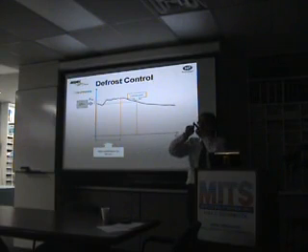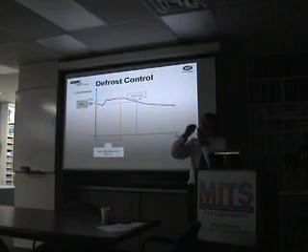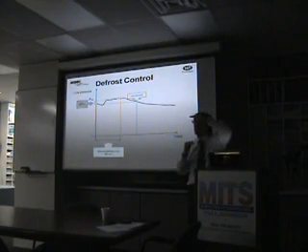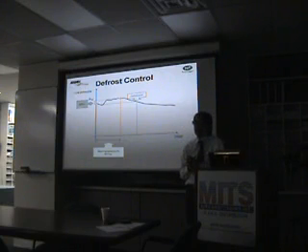During the hot gas injection, we check the pressure. If we are able to recover the 0.4 bar, it means that the hot gas was just enough to clean the coil from the first frosting. But if we end the cycle and we didn't recover the 0.4 bar within the maximum time, which is 3 minutes of hot gas injection, we invert the cycle and we are sure to clean the coil completely from the ice. So you almost have two stages of defrost.